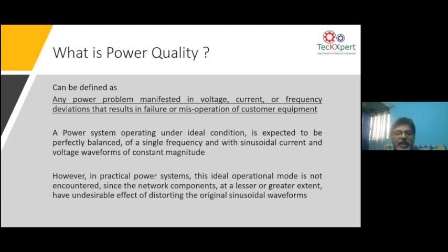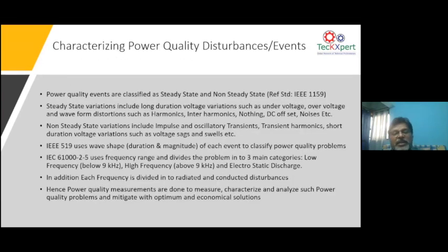A power system operating under ideal conditions is expected to be perfectly balanced. However, in a practical system this ideal operational mode is never achieved, because the network components substantially affect the original sinusoidal waveform shape. Now, there are different ways of characterizing power quality problems. Power quality has two situations. Certain power quality problems are steady state, and certain problems are non-steady state, which means they come and go, with random behavior. In a steady state, you can take undervoltage, overvoltage, harmonics, noises, and DC offset.